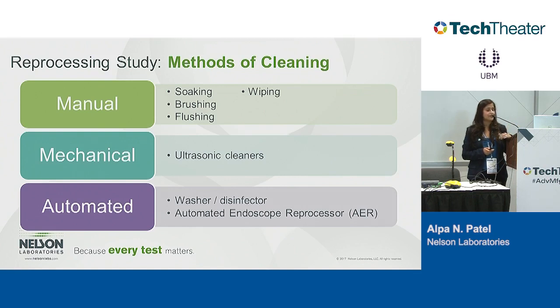If you go to the healthcare facility, you will see that manual goes in first. They will pre-rinse the devices. Then it will go in a sonicator if the product allows that, and then goes into the automated washer. So all 3 are usually used. However, they cannot be validated as one system. They have to be validated separately. Mechanical fits in the manual, but manual cleaning and automated cleaning are 2 separate things, and they have to be evaluated separately.